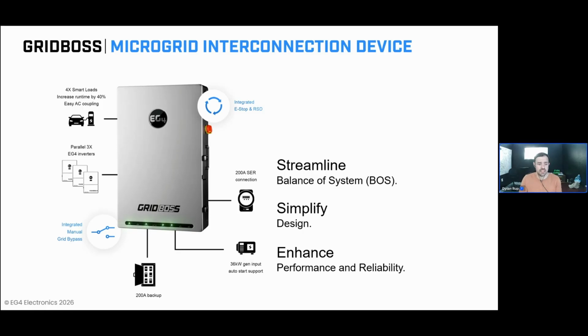Each GridBOSS does have an integrated panel board that enables you to parallel up to 3 EG4 hybrid inverters directly at the unit with no additional combining panels or combining equipment required. So it enables you to add additional capability to this system either at time of install or at a later date with essentially a single conductor run.